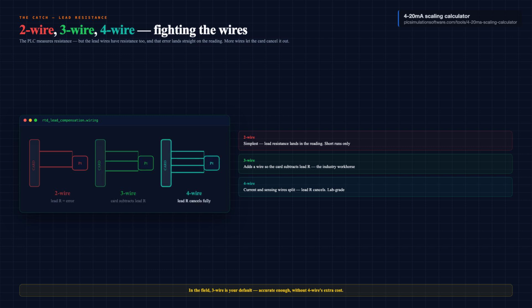A 3-wire RTD adds a third wire, so the input card can measure the lead resistance and subtract it. That is the workhorse, by far the most common in industry. A 4-wire RTD goes all the way. It separates the wires that carry current from the wires that sense voltage, so lead resistance cancels out completely. It is the most accurate, and you see it in labs and calibration.